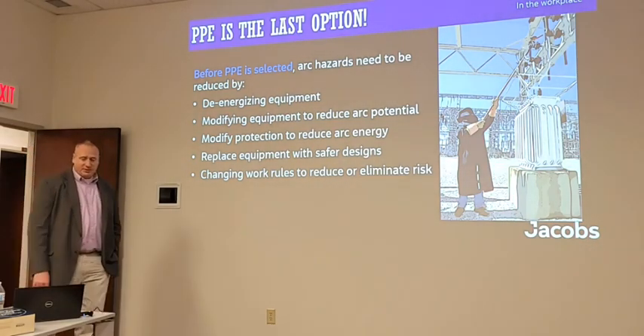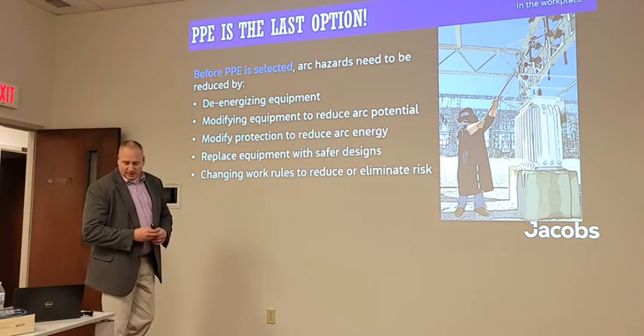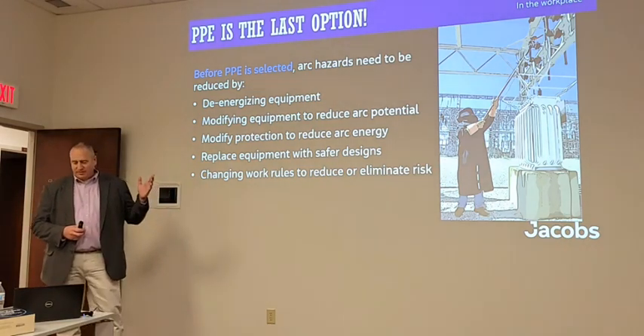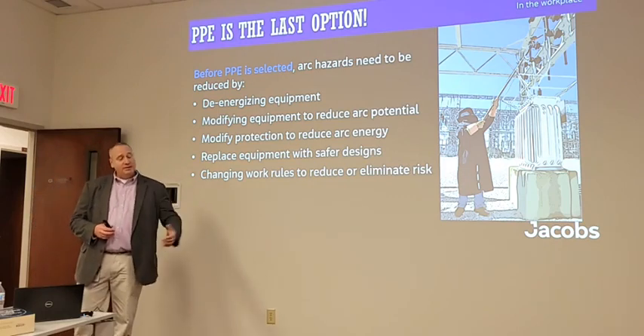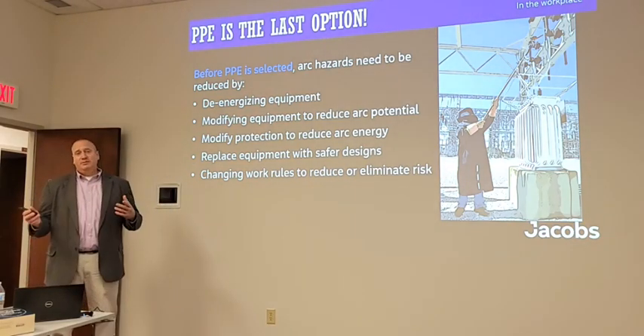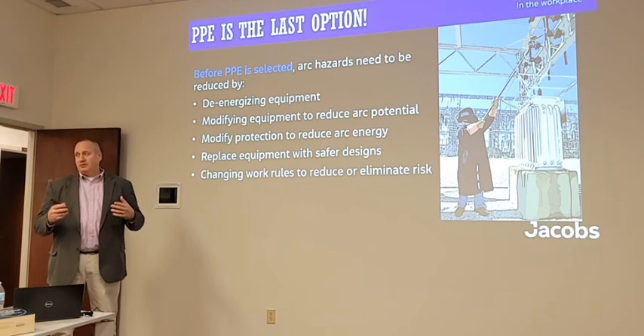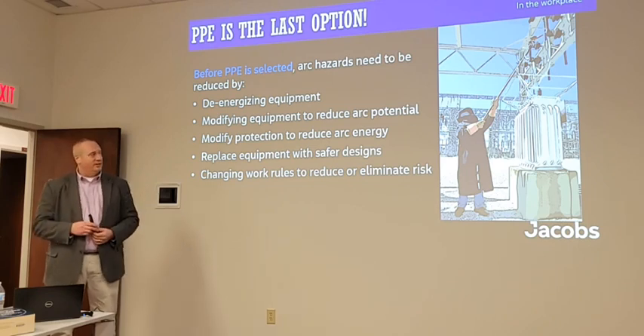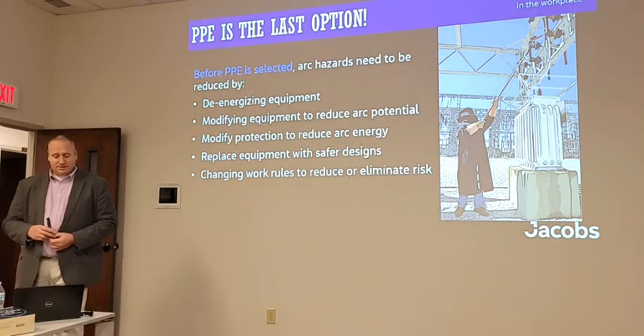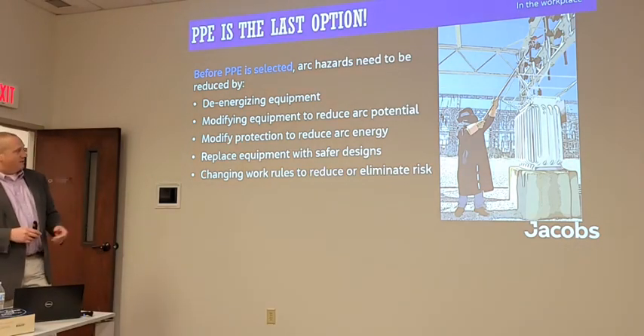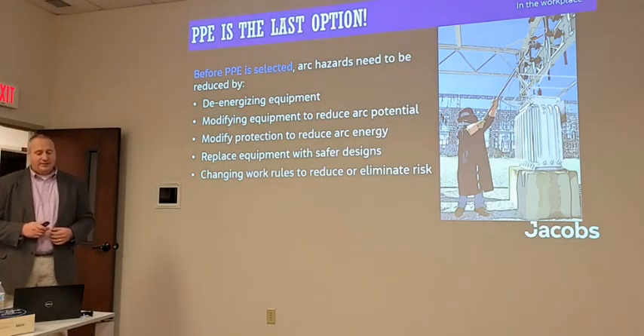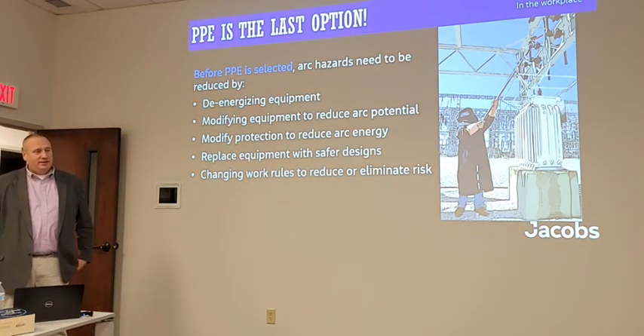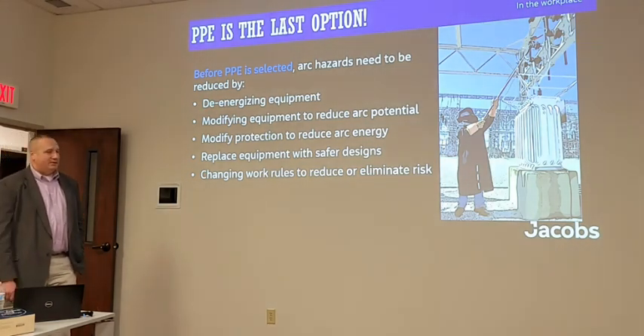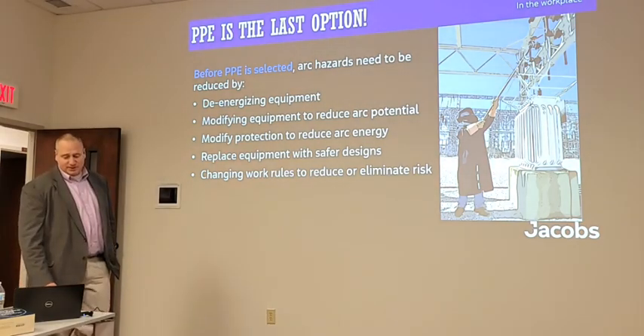You can modify equipment to reduce arc potential, modify protection. That could be the available fault current or the amount of time it takes to clear the fault. If you can make an adjustment to the instantaneous to where it's going to trip a lot faster, that reduces your arc flash energy level to where you can make it safer. Replace equipment with safer designs. The point here is your PPE is the last option. You always want to have it available in case you need it, in case you have to be exposed to the hazard, but it's the last option. We want to work through the hierarchy of risk control methods first.